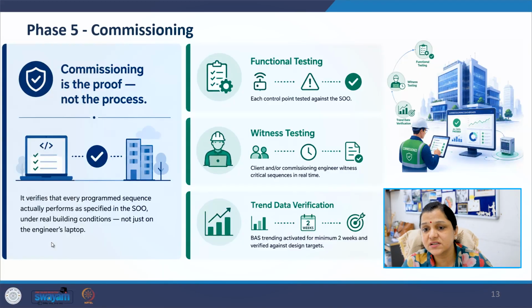In phase 5, the commissioning phase, which is one of the most important phases in the building automation system lifecycle, commissioning verifies whether the installed system actually performs according to the sequence of operations. This is not only a paperwork exercise, it requires real functional testing. For example, sensor failures and equipment trips may be simulated to verify fail-safe operations. Witness testing is also conducted. Here, the client or commissioning authority observes critical sequences in real time.